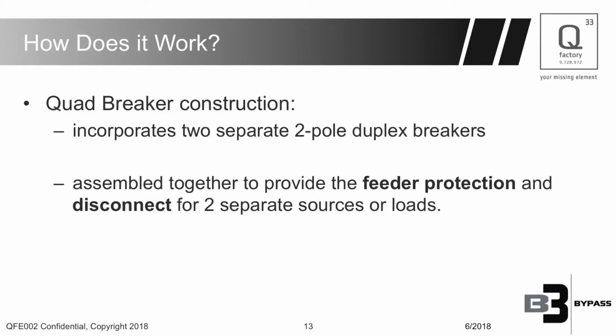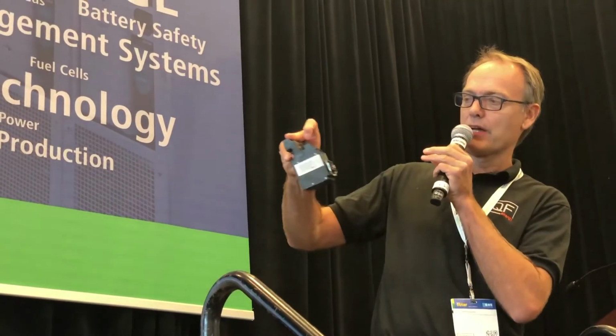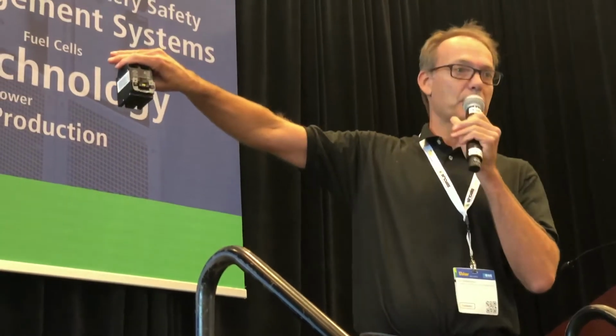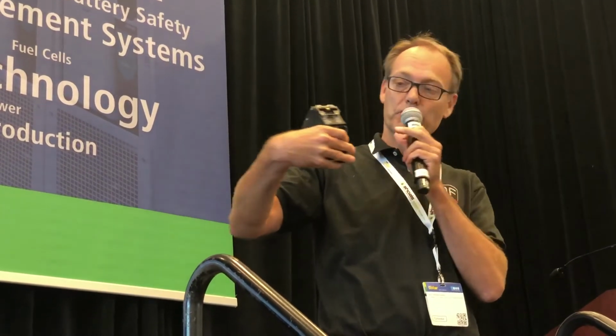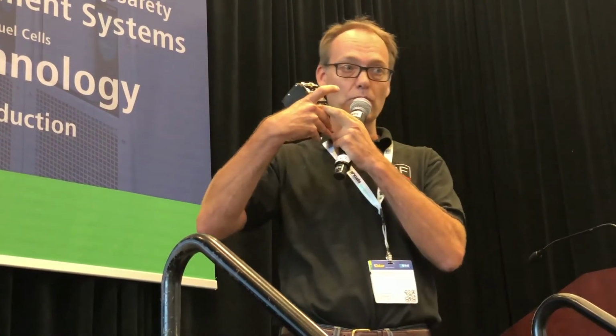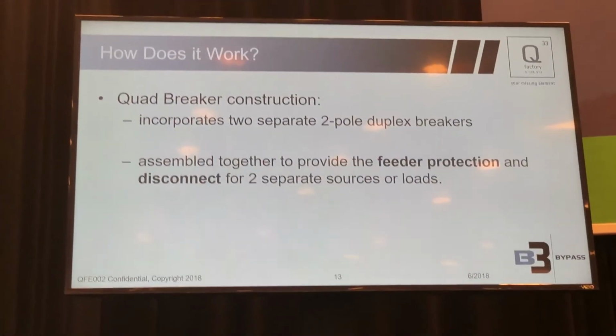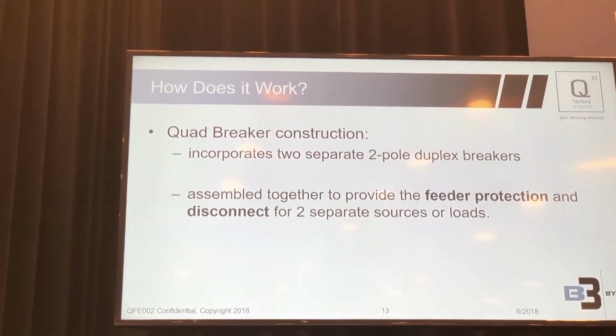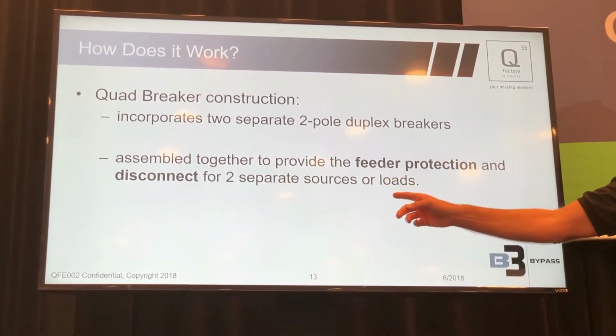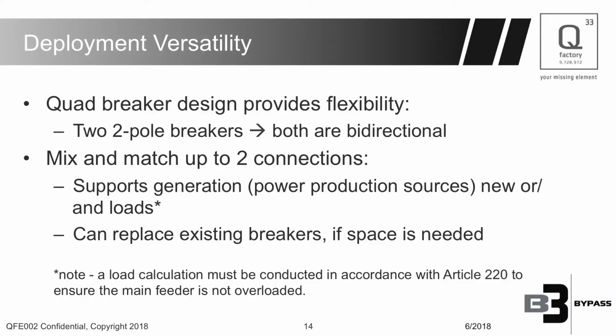How does it work? This is the actual product. If I take away this part here, it looks like a typical breaker. This would be a quad breaker, which means it's two 2-pole breakers, which means we have 2 points where we can put in 2 different generation sources or 2 different loads or a combination of each. So this is like any standard 2-inch format quad breaker. The difference is the bus bar that allows us to attach directly to the line side. Since it is a quad breaker, it's assembled together and it provides feeder protection and disconnect for 2 separate sources or loads. The benefit of being a quad breaker is you can mix and match sources and loads.